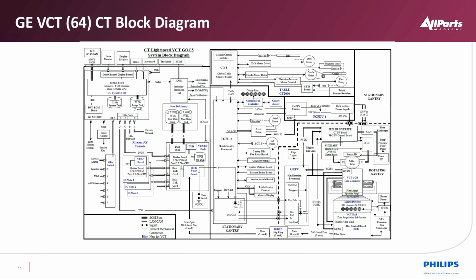Here's an example of a GE VCT that represents a true block diagram of a product that's out there. We actually have one of these as a bay. And if you come to training here, this is one of the systems that is also used for training as well. So you can see that we have a little bit more detail, but we still basically have the same elements: an X-ray tube, X-ray generator, filament control, KV control, high voltage tanks, and then we have a collimator that manages the aperture size, and we also have different filters in there.